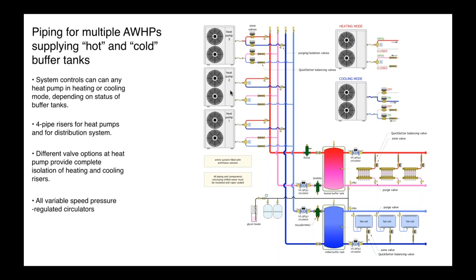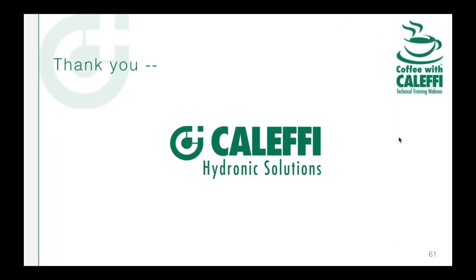And of course, it could be two heat pumps, it could be four heat pumps. I've seen systems that have upwards of six of these. There are larger capacity commercial units that get up into a three-phase, 10-ton, 20-ton output configuration. So you're dealing with a 40-ton load, you probably aren't going to put together 8 5-ton heat pumps. Probably going to put together maybe 2 20s or 4 10s. So the concept of how to pipe those independently into these two different buffer tanks, you have the ability to do simultaneous heating and cooling. And that's it on my slide.